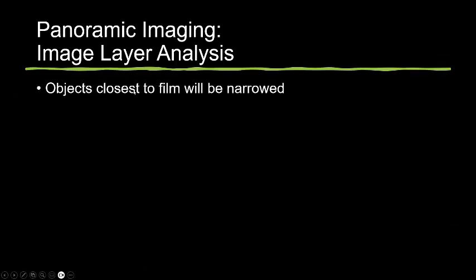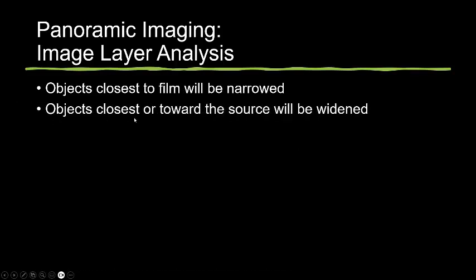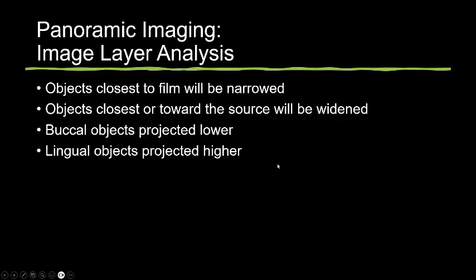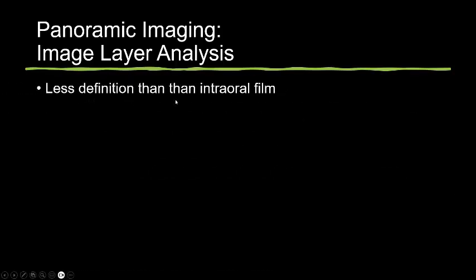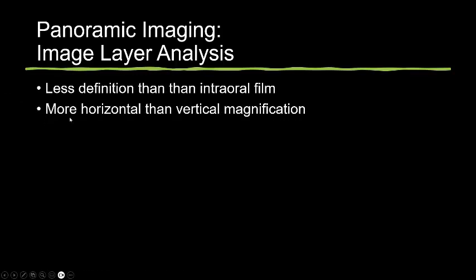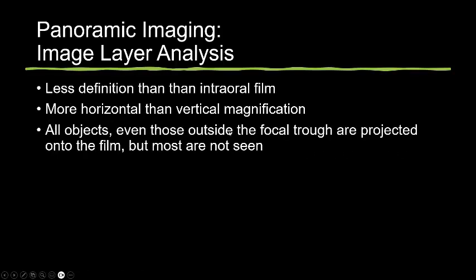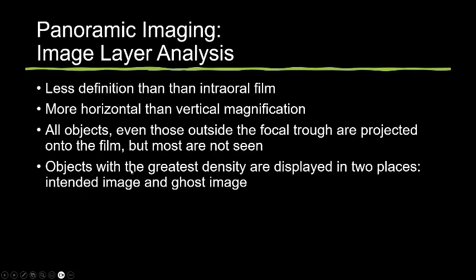Image layer analysis: objects closest to the film will appear narrowed; objects closest to the source will be widened. Buccal objects are projected lower, while lingual objects are projected higher. Objects in the center of the layer are magnified approximately 20 to 30%. There is less definition than on intraoral film, and definitely more horizontal than vertical magnification. All objects, even those outside the focal trough, are projected onto the film, but most are not visible. Objects with the greatest density are displayed in two places — the intended image and a ghost image.